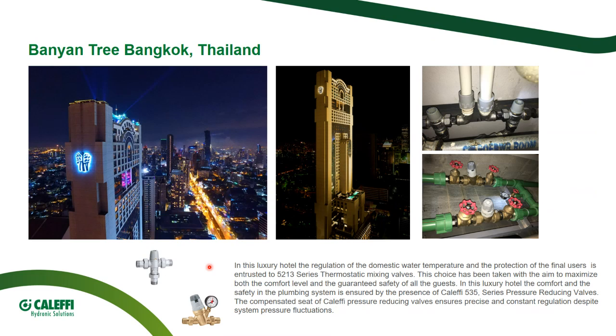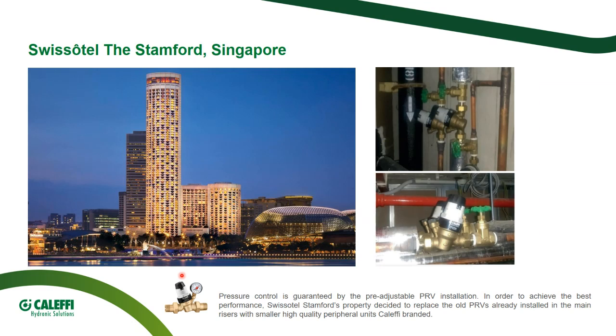But also in Thailand, they pay attention to this. They installed in the Banyan Tree Bangkok, a very, very high star rated hotel, some pressure reducing valves in parallel, but also every single room is equipped with an anti-scald thermostatic mixing valve. Also in Singapore, they decided to regulate with a Caleffi pressure reducing valve for both hot and cold water. This is Swissôtel The Stamford. This one was a recent application.